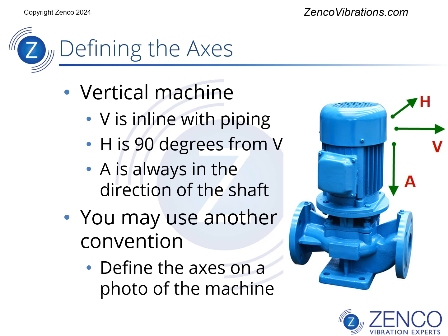Defining axes in a vertical machine gets a little tricky because axial is always with the shaft, and in this case axial is also vertical. So we need to define vertical a different way. A common way to do this is to consider vertical to be in line with a discharge pipe, and horizontal would be 90 degrees from vertical. You can use a different convention — just either draw a picture or take a photo, label the axes on it, and make it clear to everyone how you're defining vertical and horizontal.